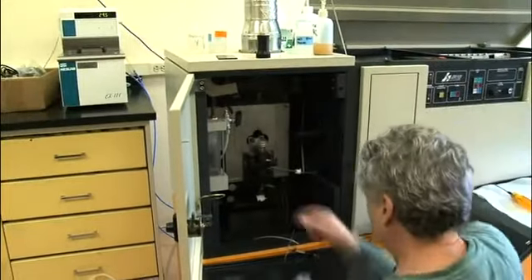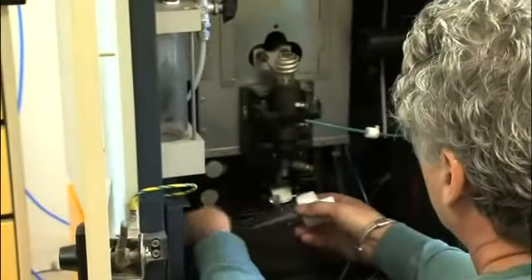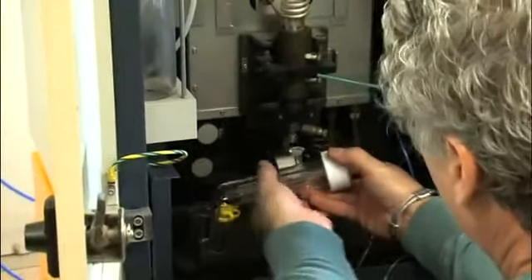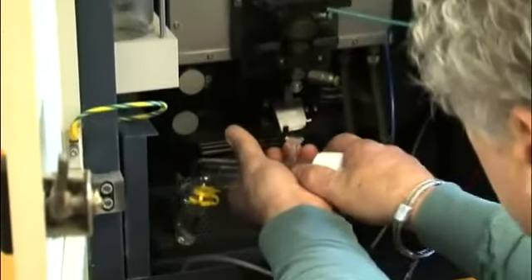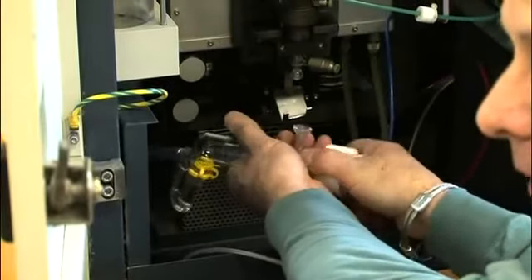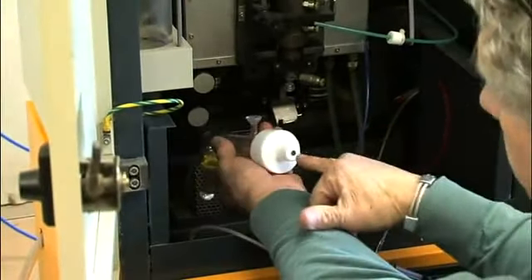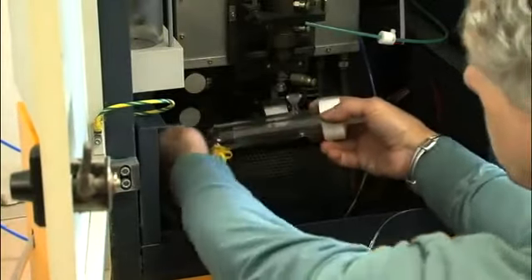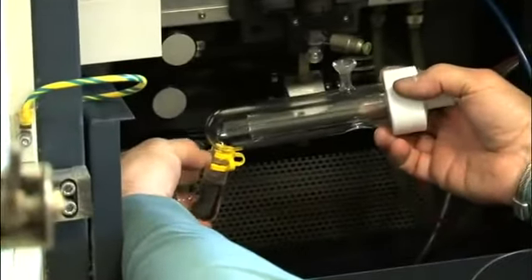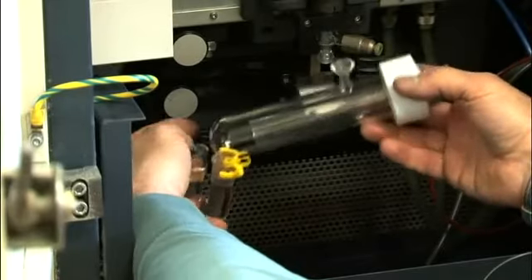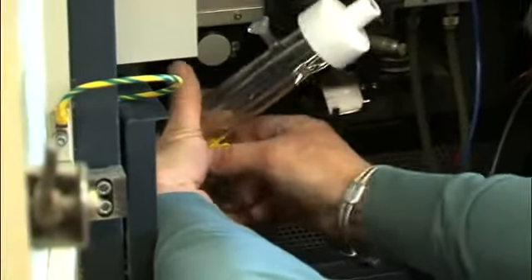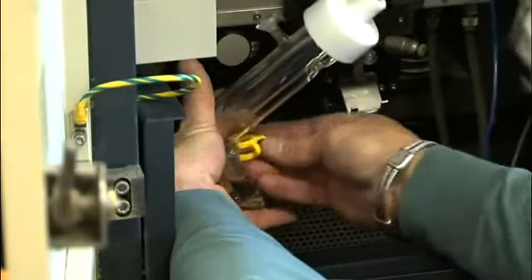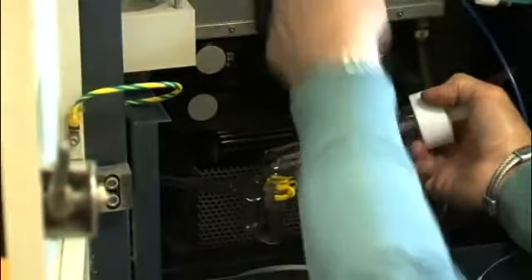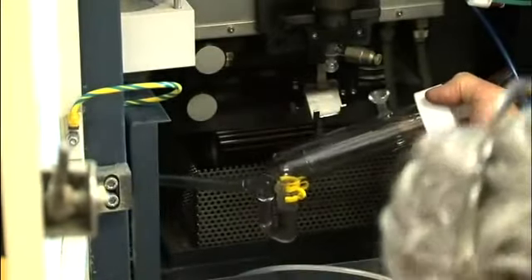Okay, spray chamber. Now, this comes off, but it's not wanting to come off, so I'm not going to force it. I might crack it. There's an O-ring in here. There's an O-ring here for the nebulizer where that plugs in. Your drain should come off, but it's not coming off, so I'm not going to force that either. To get that off, you take this clamp off, and then it should separate. There's just frosted glass. You always have to have water in the drain.